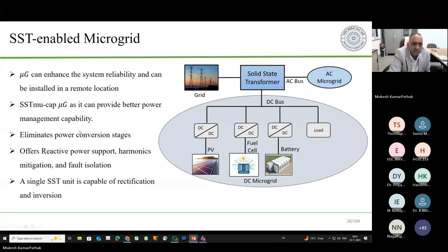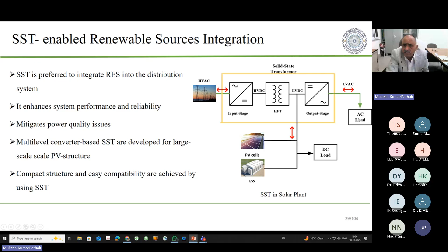If you want to use this for renewable integration, the solid state transformer setup looks like this: a high voltage AC grid, input stage, HVDC, high frequency transformer, low voltage DC, and output stage. Now your distributed generation or renewable generation system can be directly connected here without needing another converter, because the voltage needs to be brought to this level. So you use a DC-DC converter, not a DC-AC converter. Similarly, here also a DC-DC converter feeds the DC load, and on the output side you can connect an AC load.